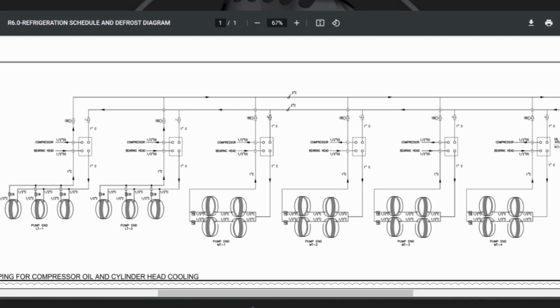Okay. So it's just on the 4 high stage compressors, and ammonia when it's compressed gets very hot. The discharge temperature approaches 250 degrees, and it'll cook the oil and it'll cook the compressors. So we're pumping from our condenser water. We're pumping about 10 GPM into each compressor, and Carlyle's recommendation is to run it through one head. If you look at their manual, you go through one head, you go to the next head, then you go to the next head on a 5H80.